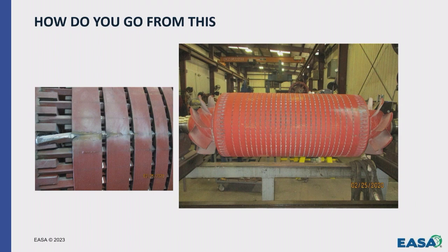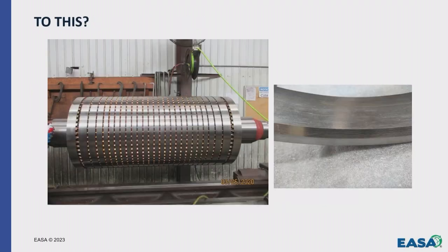So this is your typical aluminum 2-pole fabricated aluminum rotor. In this one, the bar is broken. It's already started to lift through the iron, and eventually, I think it was caught before it took out the winding. So if you want to know how to go from an aluminum rotor like this to a copper fabricated rotor like this, it's the advent of these stainless steel rings, and that's in the right side picture there. Those stainless steel rings are made from a non-magnetic material. They're applied with a pretty heavy interference fit. They're installed over the machined surface of the shorting rings, and we also run them over the top of the bars because they add support to the bars.